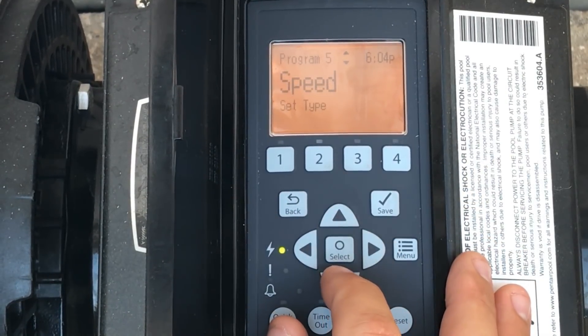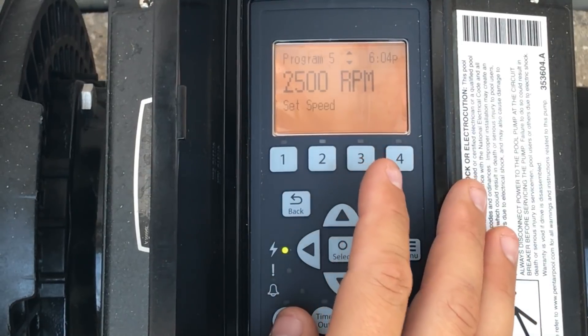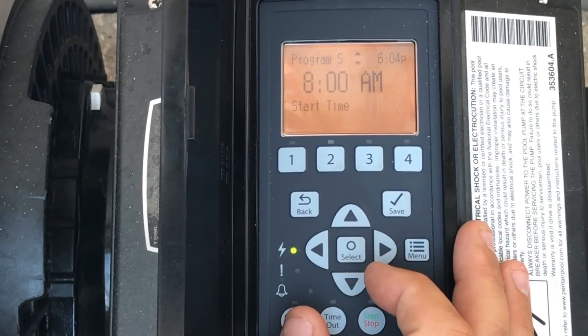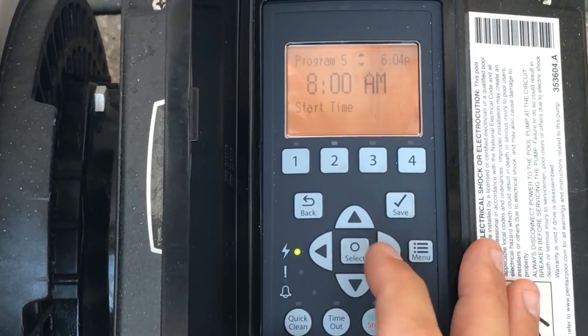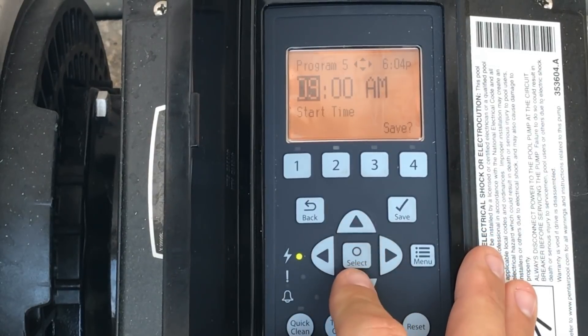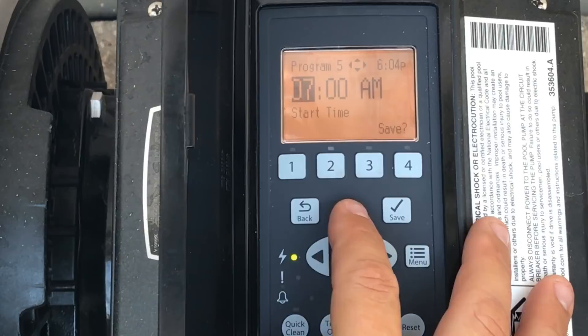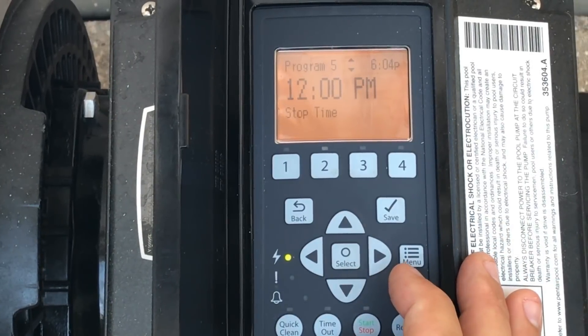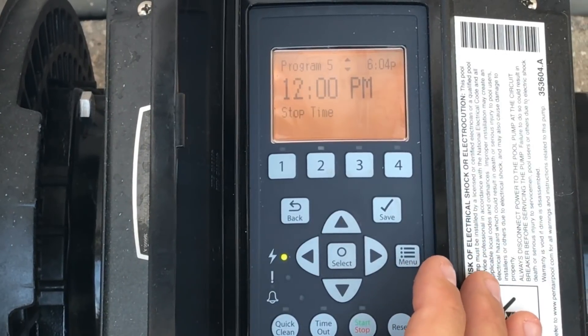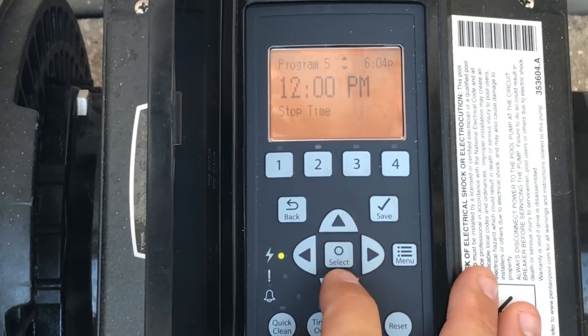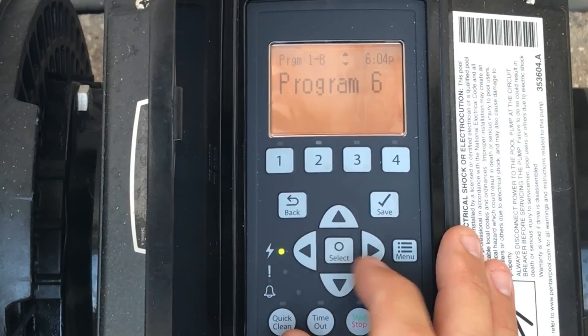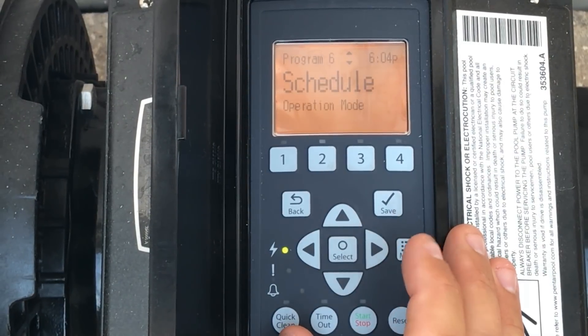Schedules trump everything else. For program five, set the speed type to speed, RPMs at 2500. It starts at 8 AM — if you want 7 AM for instance, hit select and use the arrows to adjust, then hit save. The stop time is 12 PM.